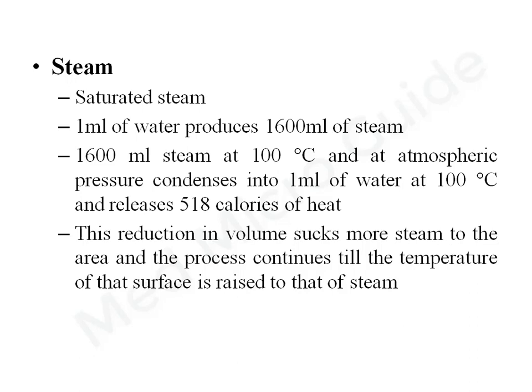If we heat 1 ml of water, it produces 1600 ml of steam. If that same 1600 ml of steam at 100 degrees Celsius at atmospheric pressure condenses into 1 ml of water at 100 degrees Celsius, it releases 518 calories of heat onto the article. This latent heat transferred will heat the article or medium kept inside the autoclave.